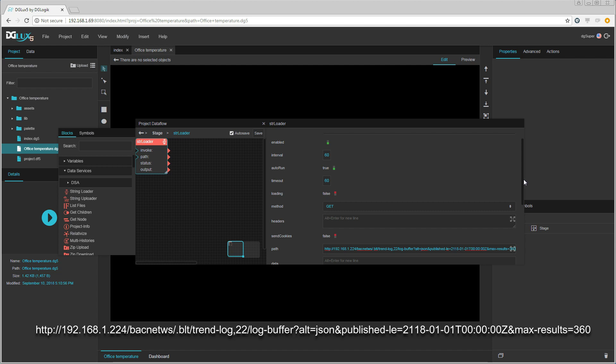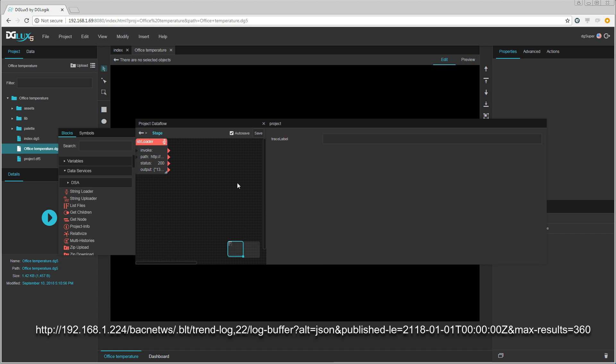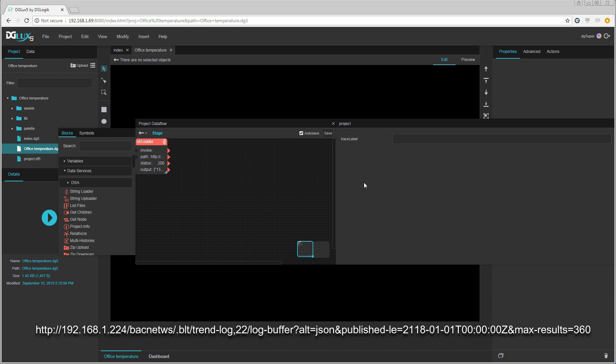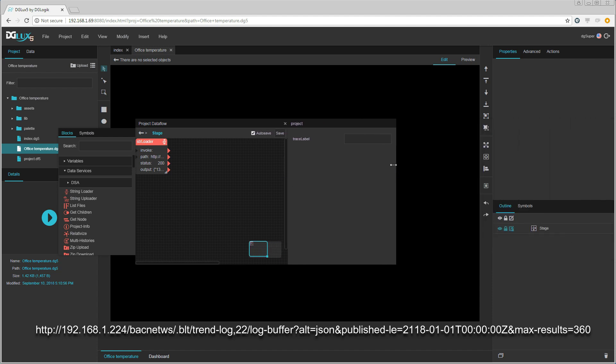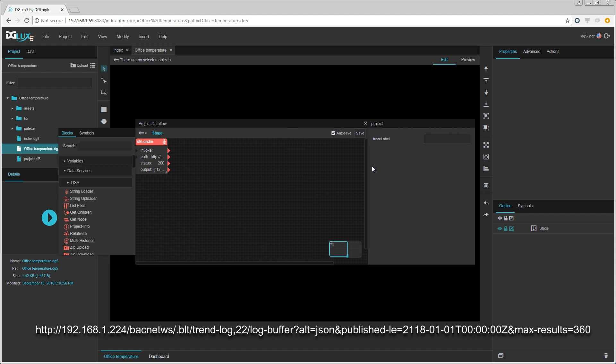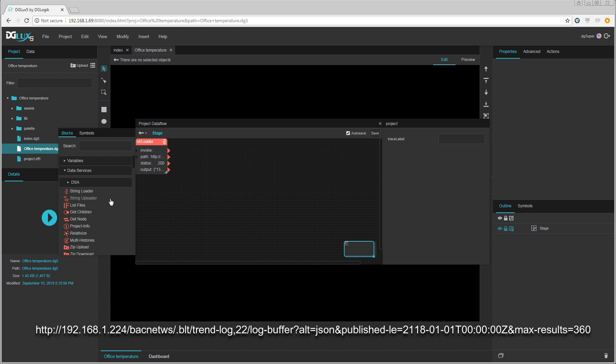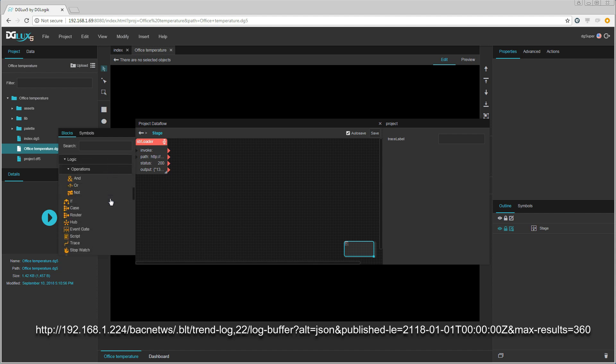We also need a path that points to the trend log that we are going to read from. I am going to use a path that gets data that is older than a date that is 100 years in the future, and I only want 360 values. I want the data in JSON format. This will always give me the latest 6 hours of data.